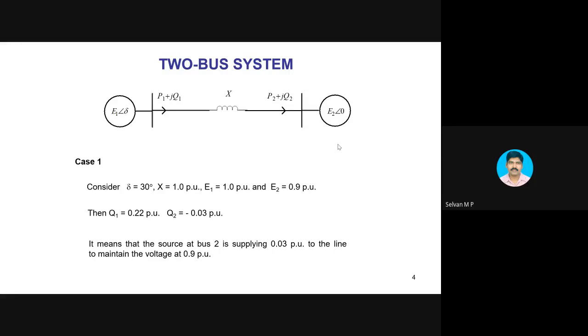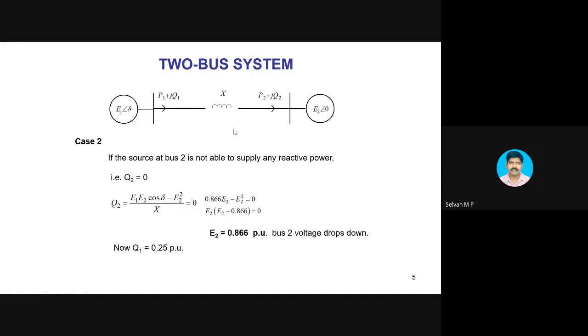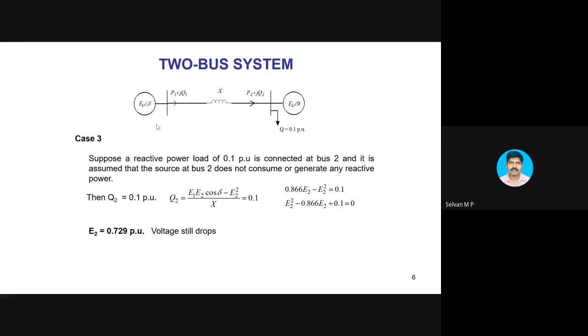So here what we learned is, when you adjust the voltage, a difference will be there if any reactive power flow is there. In reverse, you have to understand that if you want to make a reactive power flow, then you need to have a voltage difference, right? So here you can see the first case, this is 1 per unit, this is 0.9 per unit. So 0.22 per unit reactive power flows from here, 0.03 flows from here. In the second case, this is 1 per unit, this is 0.86 per unit. So now 0.25 per unit of reactive power flows in this line. In the third case, I increased the voltage difference, then the reactive power flow is also increasing, right?